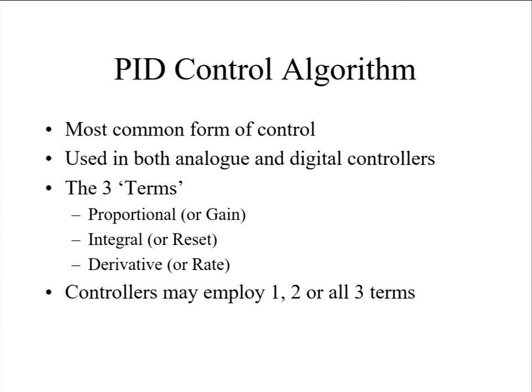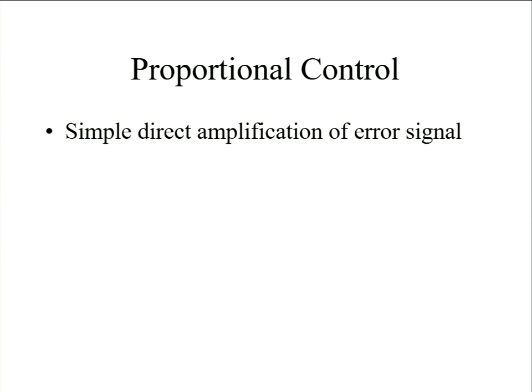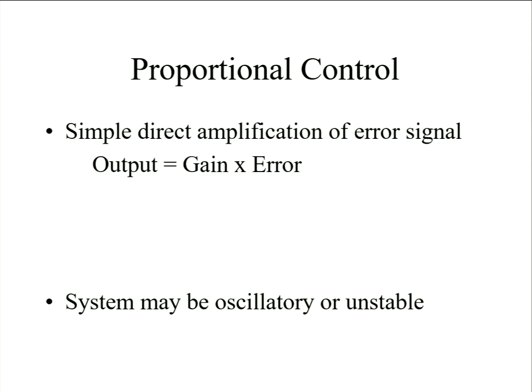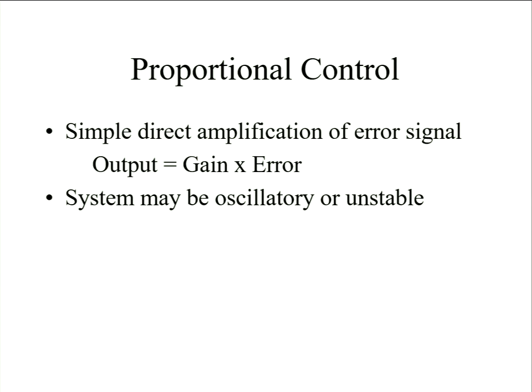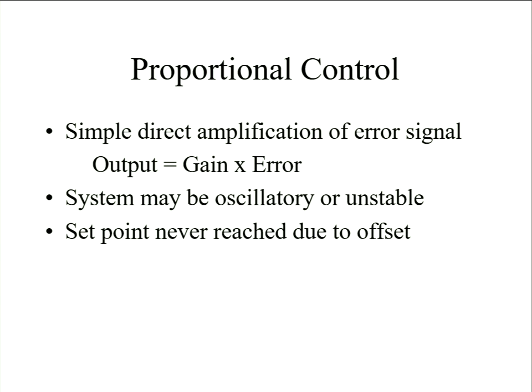Now, you've got to be careful. You can't just keep cranking gain up, because you might end up with an oscillatory or even an unstable process. So your valve going 0 to 100% open, back. Now, one thing is that to have an output of non-zero, it means by implication you've got to have an error that's non-zero. So in principle you can never quite reach your set point. You have an offset. You can try and overcome that by having some form of bias or reset, which is probably easily explained through the diagram on the next slide. But it is one of the disadvantages of proportional control. It's nice and simple, but doesn't get rid of all your error.